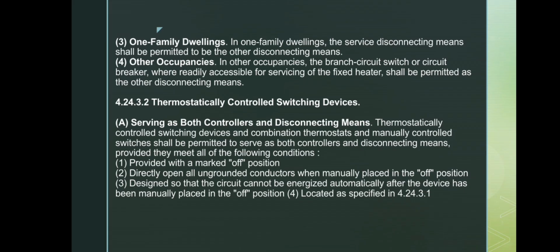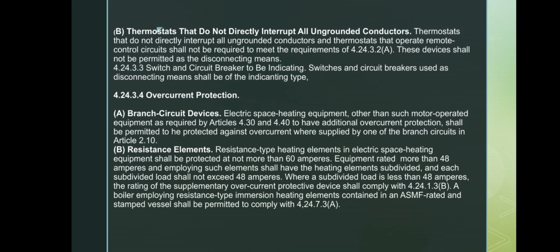The device must be installed in the proper location following section 4.24.3.1. Next slide covers thermostats that cannot be used as disconnecting means. Thermostats that do not interrupt all ungrounded conductors: if a thermostat does not directly open all ungrounded conductors, or if it operates a remote control circuit, it does not need to meet the previous requirements. However, these types of thermostats cannot serve as the disconnecting means.